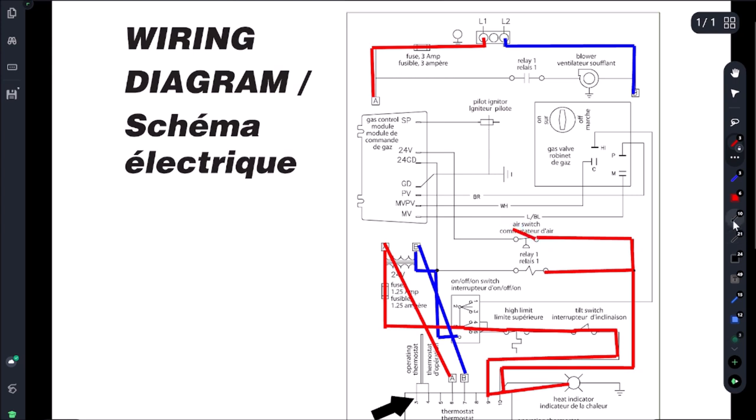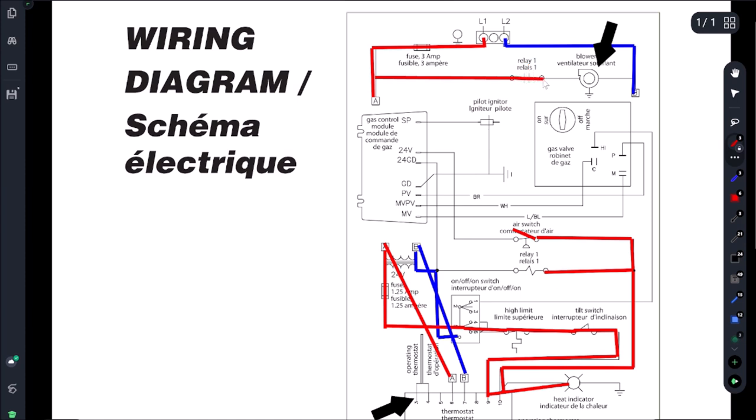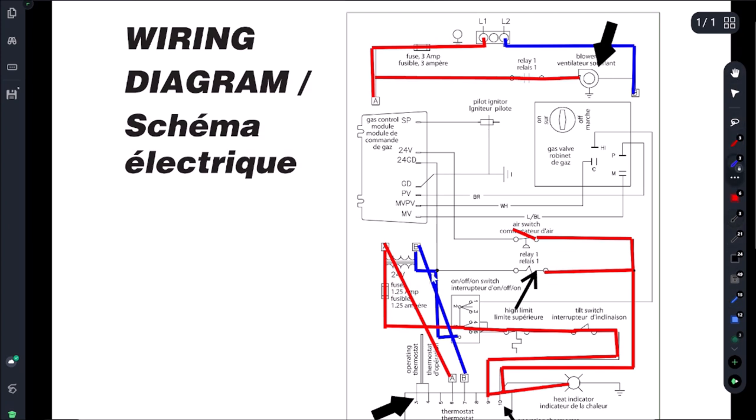It's going to be right here, this combustion blower. So how the combustion blower gets power is we're coming through this relay - this relay's open unless we have a coil close - and our coil is closing right here because we got power off of pin 10, and then the coil will get its second side of power from here and that completes the blower circuit. The blower circuit needs to be complete.